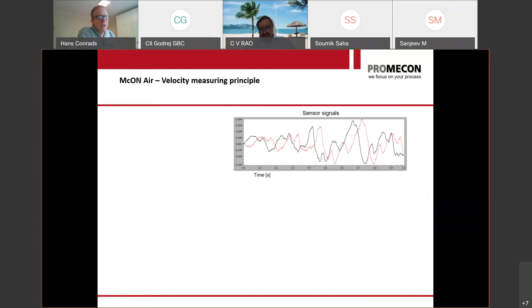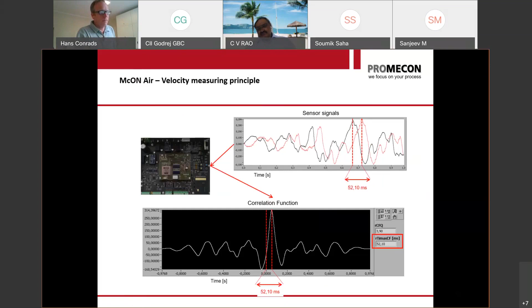However, these two signals are time shifted, right? So what Promecon is doing, we are calculating the time shift between the two signals. So we are measuring a time shift between two sensors. So time and distance of the sensors gives you velocity, right? So actually, in a nutshell, our systems measure velocity in a digital way by time shift. And by this, you have an accurate velocity and airflow reading over your whole boiler, over all 20 burners, over all 20 secondary airs, over all the mills. And that allows you to have the correct airflow distribution in the boiler. That's the first very important point to optimize your boiler.